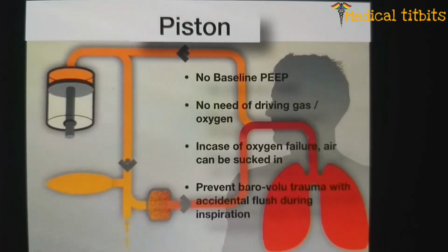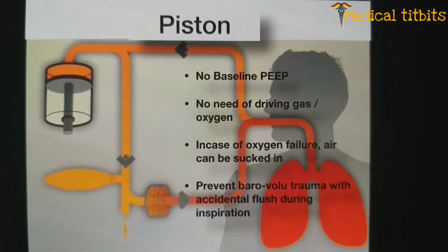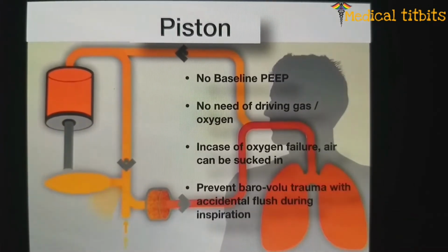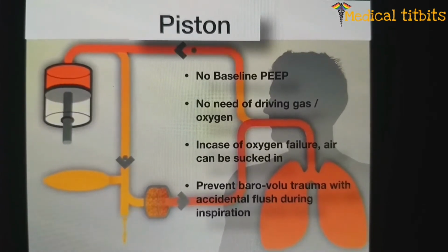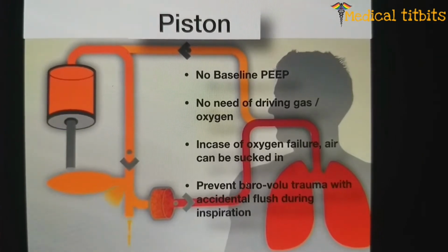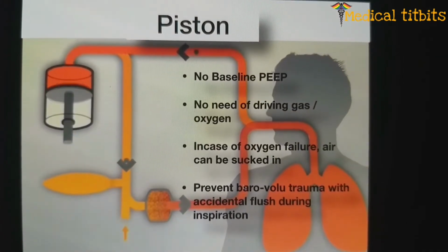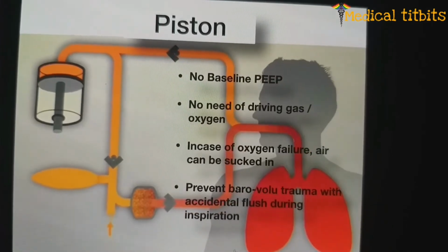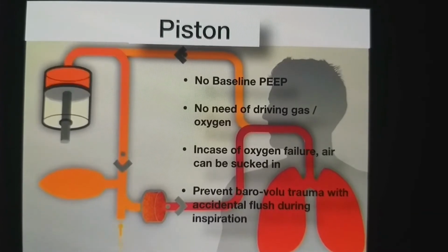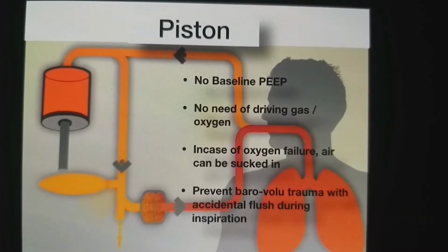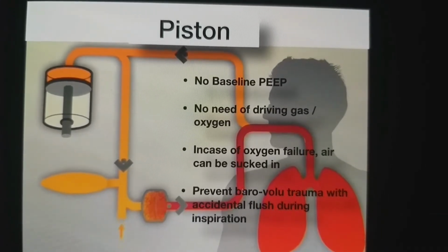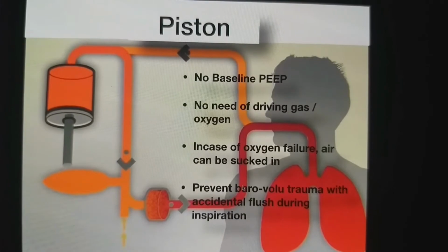In expiration, when the piston is pulling, the gas is delivered from the reservoir as well as fresh gas. So there is no baseline PEEP with the piston. You don't need any driving gas or oxygen. In case of oxygen failure, there is a provision for air to be sucked in, so your ventilation can continue. Of course, your anesthetic agent will not be there and your oxygen will not be there. But yes, ventilation will continue for some time and it will give an alarm. And this also prevents barotrauma with accidental flush, which we have already seen.